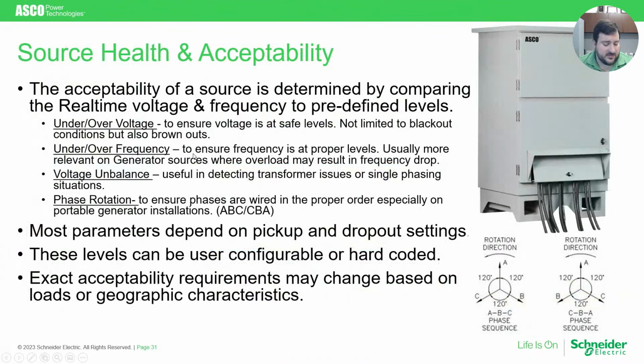One of the primary requirements of the controller is to determine the source health and the acceptability. So using the voltage and frequency, which is what most ATS controllers need to sense at a minimum, we can determine if there's an under-over voltage situation, an under-over frequency situation, voltage imbalance, or phase rotation mismatch from what the equipment expects. The controller has a nominal parameter in it. A user can go in and decide on a range of values for what's considered under voltage or over voltage based on their application, meaning some applications, such as healthcare with an MRI machine, may be much more sensitive than, say, other equipment in an industrial plant, which is not as sensitive to small power fluctuations.